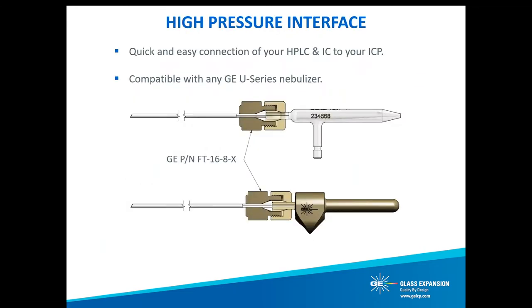The last nebulizer accessory we'd like to present is our high pressure interface kit, which is compatible with any Glass Expansion DC nebulizer model. This interface allows for an easy and reliable connection of your HPLC or ion chromatography system directly to your Glass Expansion DC nebulizer. Leaky connections to your nebulizer will affect both back pressure and the stability of nebulization efficiency, which has detrimental effects on nebulizer performance. Our high pressure interface provides a more secure connection to help prevent these leaks. And that concludes our webinar.